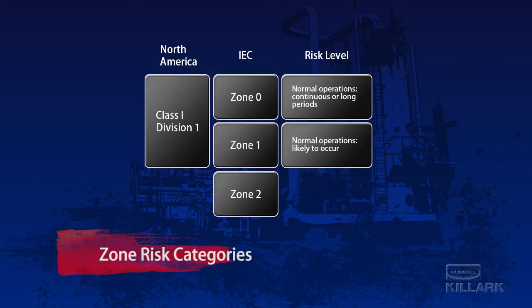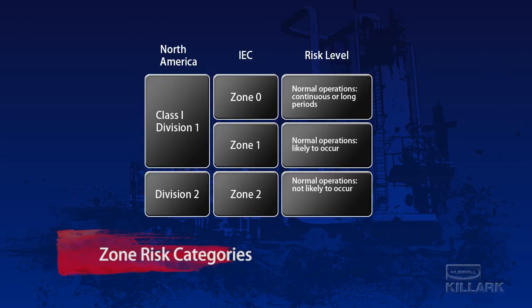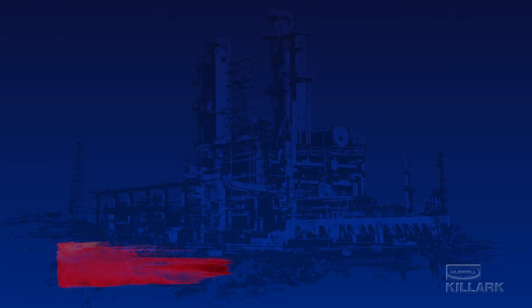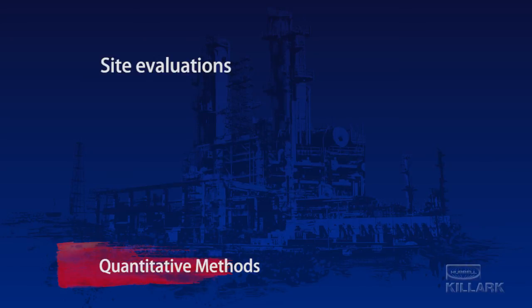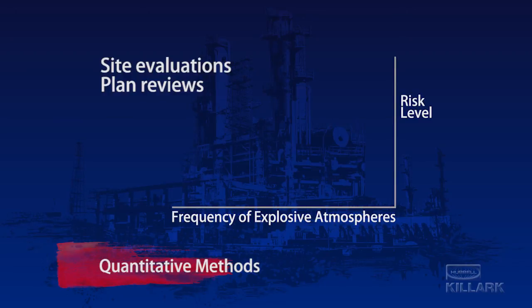The final zone, Zone 2, is identical to its North American equivalent, Division 2. Explosive concentrations are not likely to exist in the atmosphere under normal operating conditions, but failure or abnormal circumstances could cause a temporary risk of a flammable atmosphere. While the intention of the risk categories is certainly clear enough, those with the responsibility for conducting site evaluations or plan reviews to determine which risk category should be assigned often prefer to use a more quantitative analysis. There are unofficial numeric parameters that frequently serve as guidelines in the classification process.